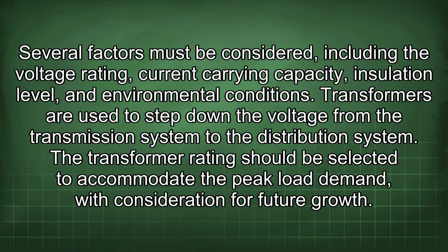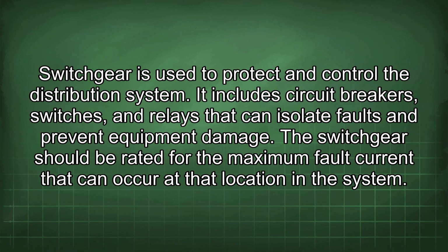The selection of equipment for a 26 kV distribution system is a critical aspect of the design process. Several factors must be considered, including the voltage rating, current carrying capacity, insulation level, and environmental conditions. Transformers are used to step down the voltage from the transmission system to the distribution system. The transformer rating should be selected to accommodate the peak load demand, with consideration for future growth. Switchgear is used to protect and control the distribution system. It includes circuit breakers, switches, and relays that can isolate faults and prevent equipment damage. The switchgear should be rated for the maximum fault current that can occur at that location in the system.